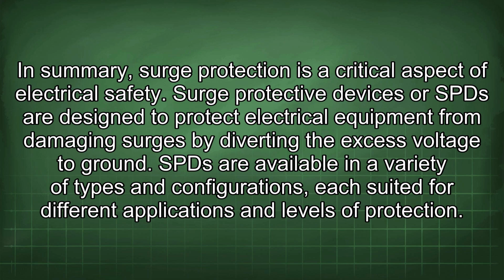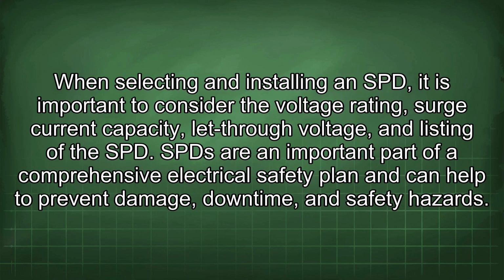Surge protective devices, or SPD, are designed to protect electrical equipment from damaging surges by diverting the excess voltage to ground. SPD are available in a variety of types and configurations, each suited for different applications and levels of protection. When selecting and installing an SPD, it is important to consider the voltage rating, surge current capacity, let-through voltage, and listing of the SPD. SPD are an important part of a comprehensive electrical safety plan and can help to prevent damage, downtime, and safety hazards.